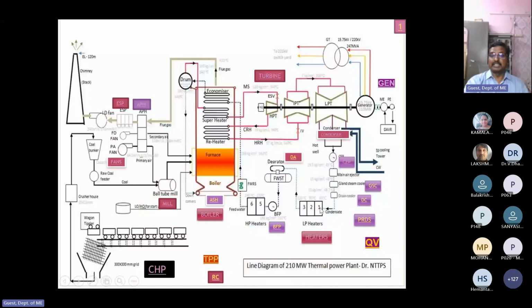The next stage is 10. HP heaters, turbines, generators, all these things are installed at 10 meters. The next one is 16 meters. At 16 meters, the deaerator and some more equipment are installed. That means from the boiler feed pump to the deaerator there is a height of 16 meters. Because of this height, it creates some suction head at the feed pump, to avoid cavitation problems.